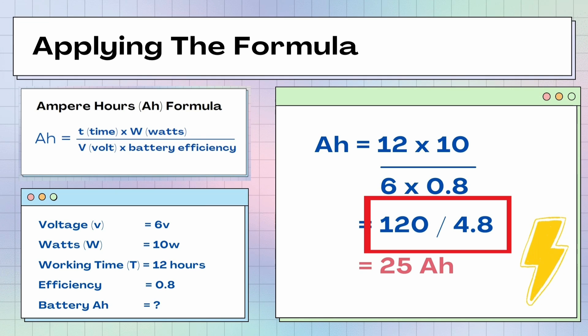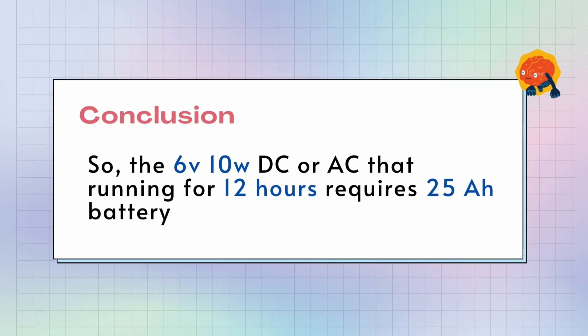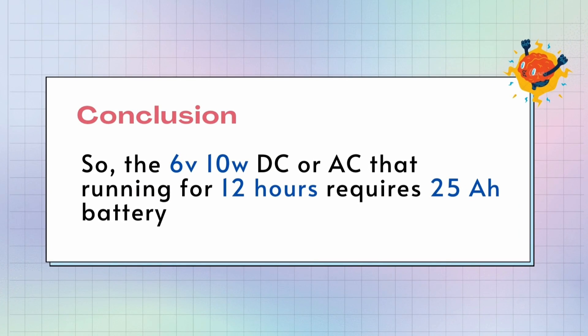And the final result is 25 ampere hours. So our battery capacity is 25 ampere hours. We finally come to the end. To summarize what we learned: we now understand the formula to calculate the battery capacity. A component with 6 volts direct current or alternating current, running for 12 hours, requires 25 ampere hours of battery.